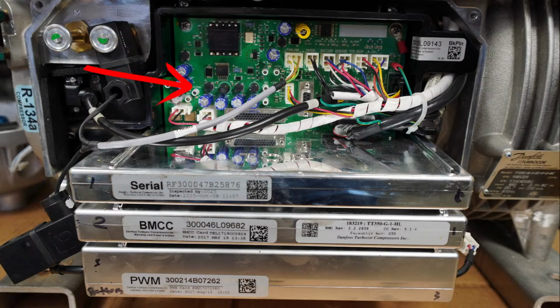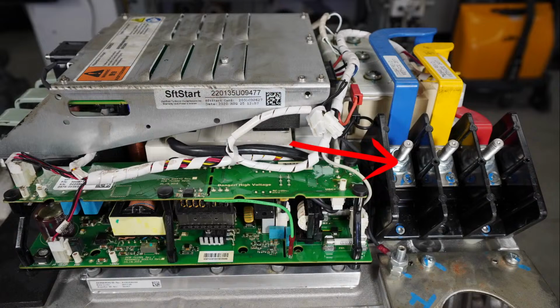If those aren't having any of these LEDs light up or anything, then that would be an indication that the whole system is not booting potentially. So the first thing I'd want to verify is my fuses here, and potentially down inside the control panel. You'll still have a power panel with typically a disconnect switch or a breaker for the whole chiller as a whole, and then it'll pass up here through this port to the Turbocor terminals, and then the larger ones will have a set of fuses here.